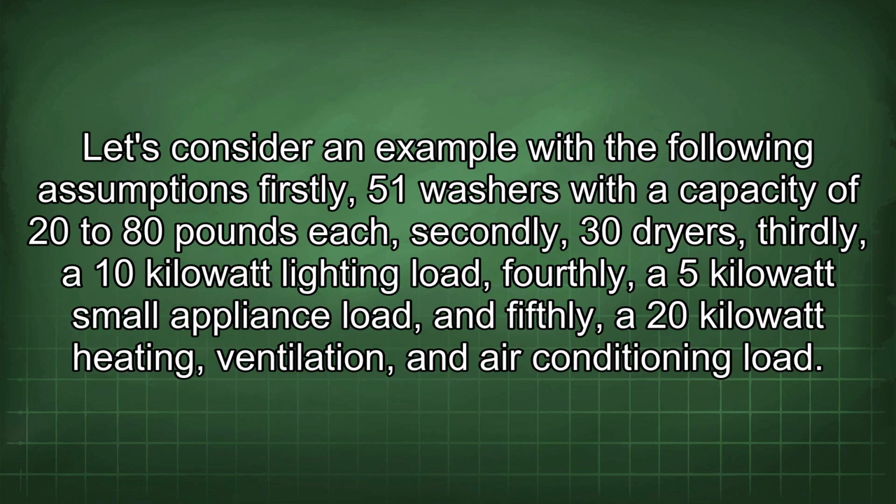Let's consider an example with the following assumptions. Firstly, 51 washers with a capacity of 20 to 80 pounds each. Secondly, 30 dryers. Thirdly, a 10 kilowatt lighting load. Fourthly, a 5 kilowatt small appliance load. And fifthly, a 20 kilowatt heating, ventilation, and air conditioning load.